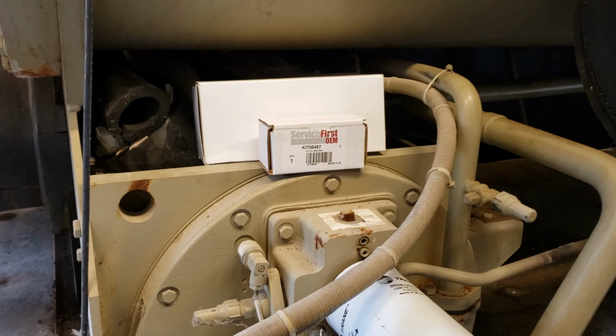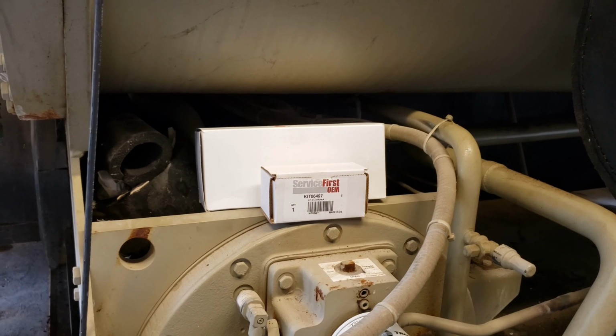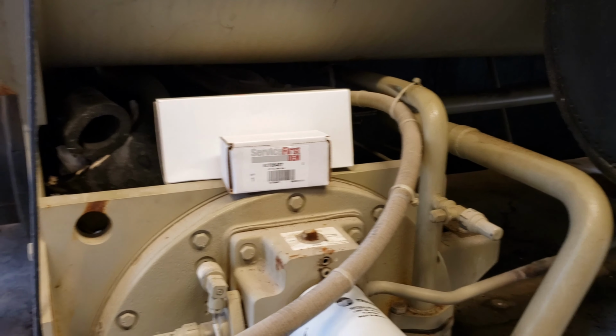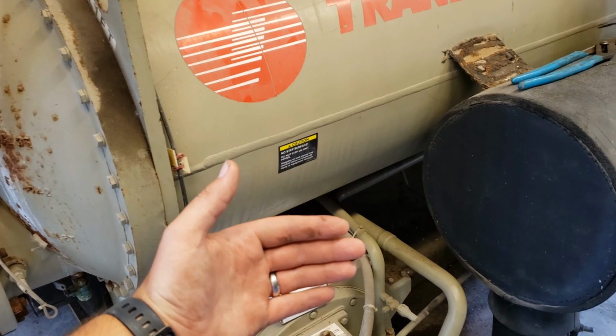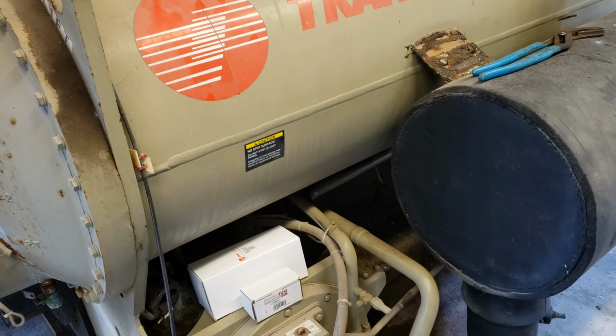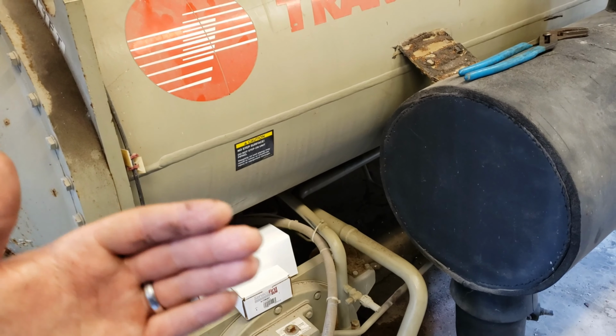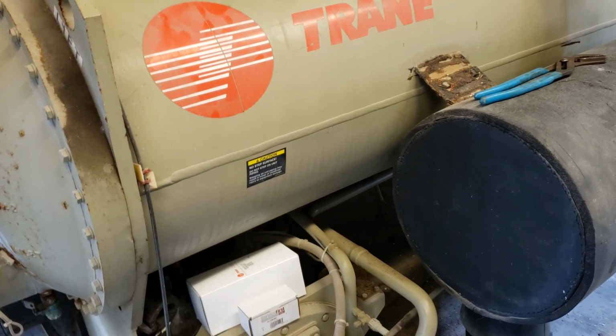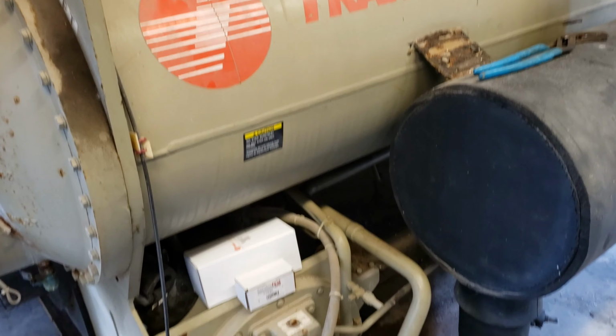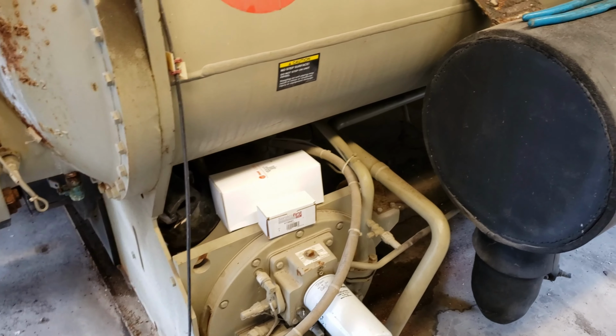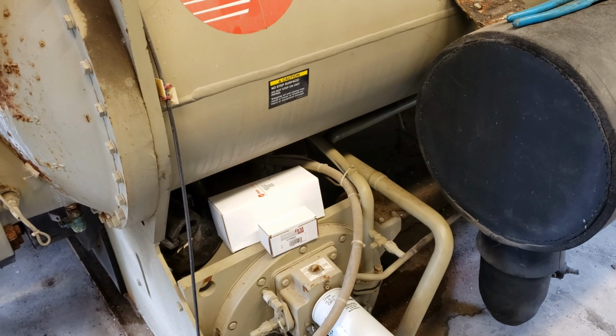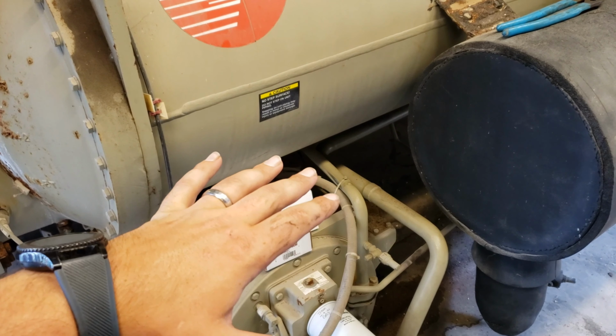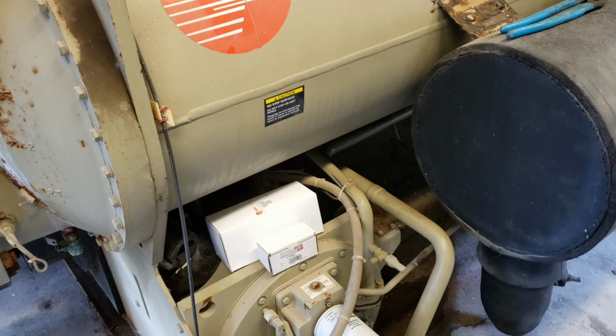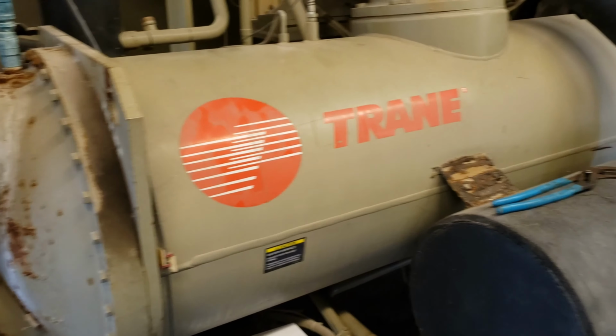So it confirmed that the oil had migrated, which means we made the right choice by not assuming that all of it had been removed from the system, and that it was just somewhere else in the system. All that oil's been returned back to the sump. We look really good. It was probably a little low on oil to begin with, and I think those 5 gallons definitely helped it for sure.